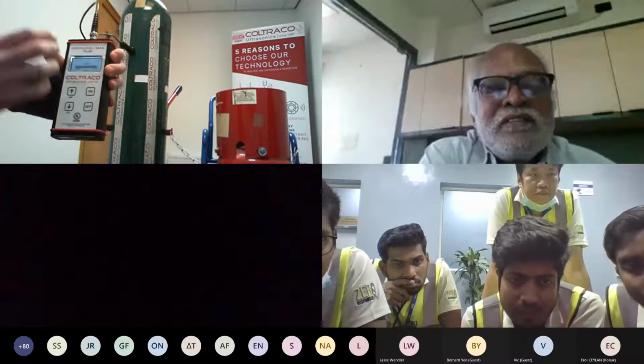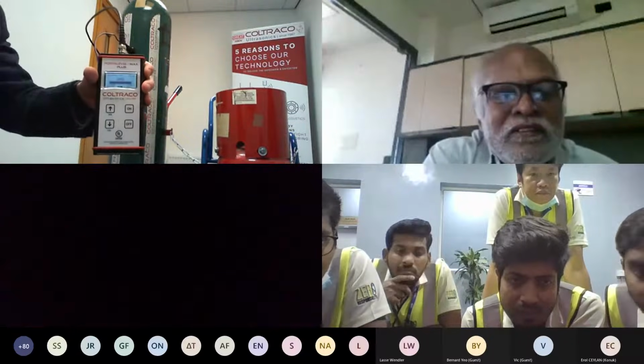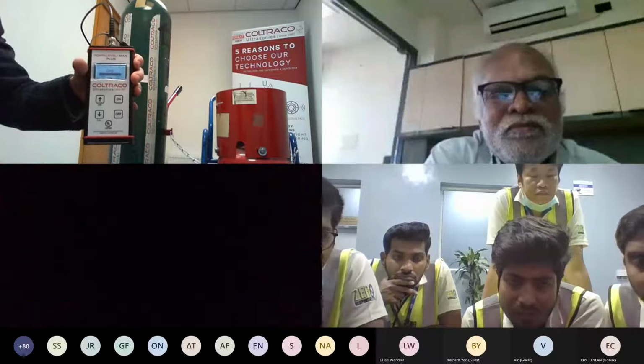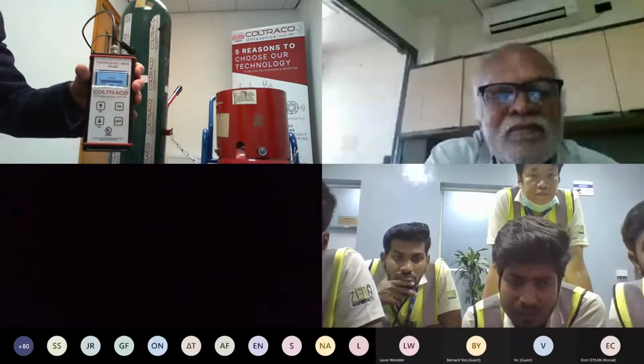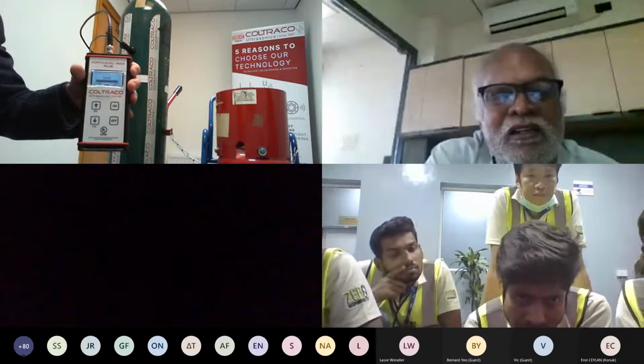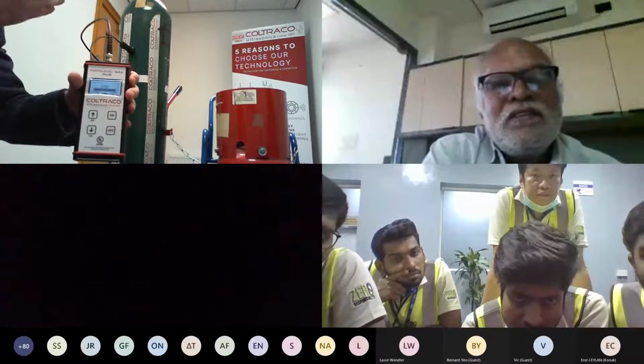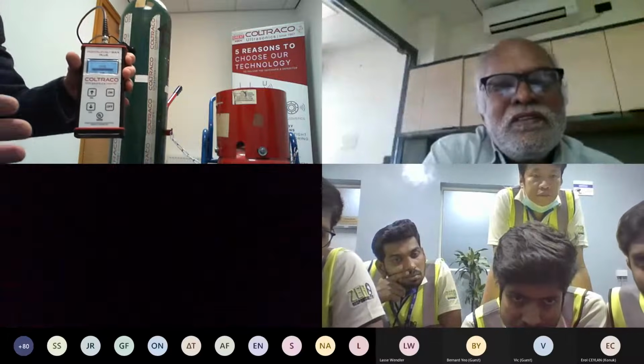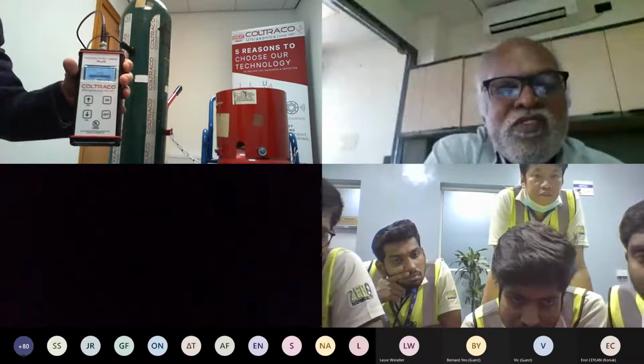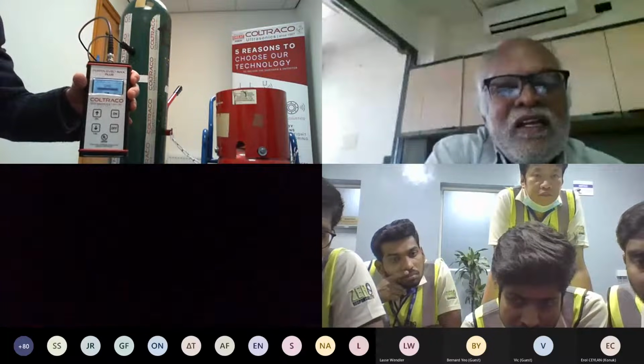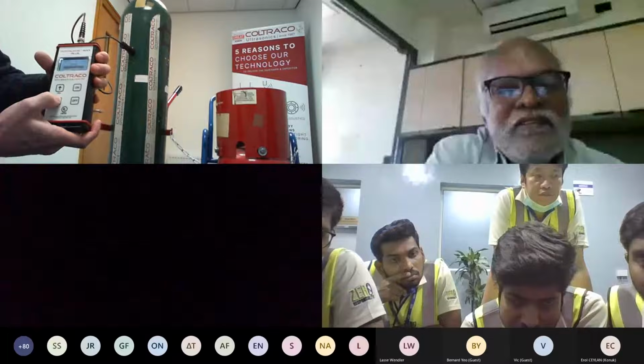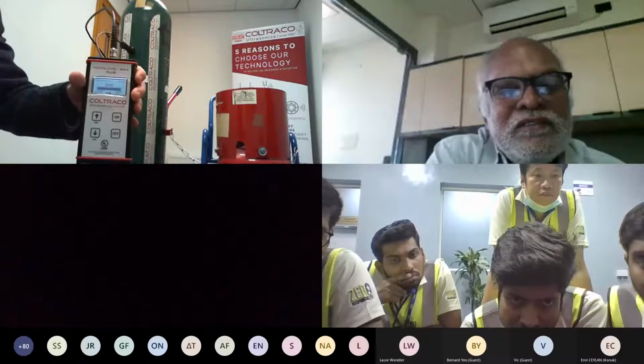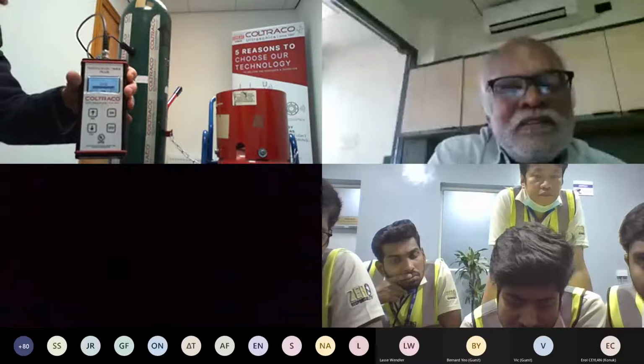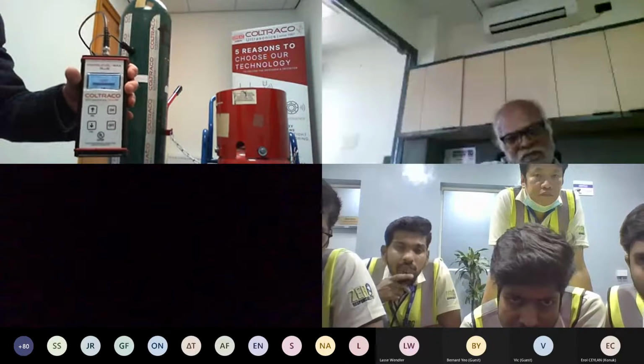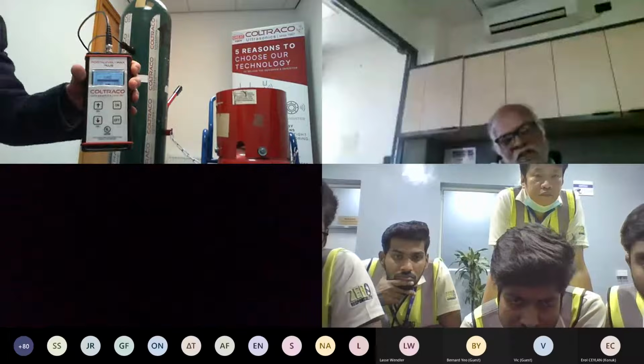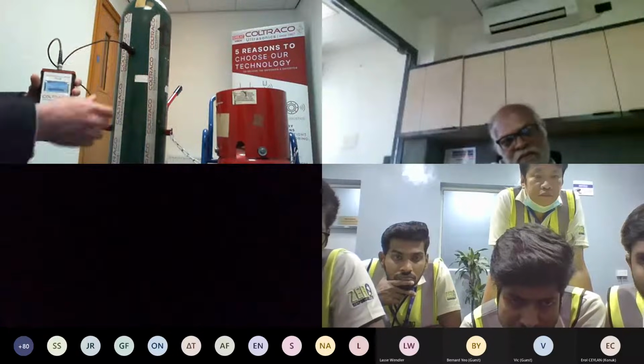For this cylinder, with the different cal modes that we have, in our manual, we describe how we use each one. So for cal 1, that is typically when the difference in the readings between where you get the high readings, in this case the gas, and where you find the low readings. If that difference is quite large, with a reasonably steep drop off, and we need to calibrate in the average high area, we can use cal 2. The reason I'm using cal 2 in this case is because the highest reading I found was around 2,600, whereas it dropped to around 500. That's quite a large drop off. So we use cal 2 in this circumstance.